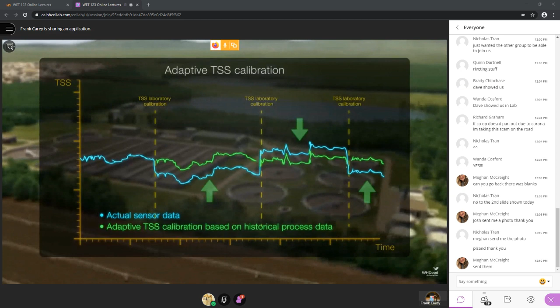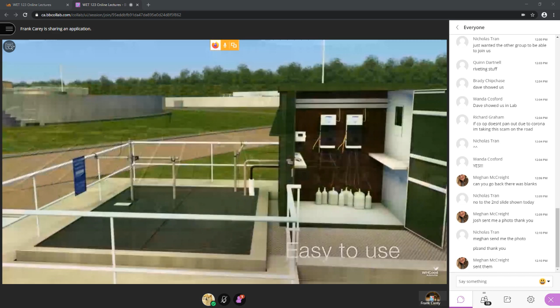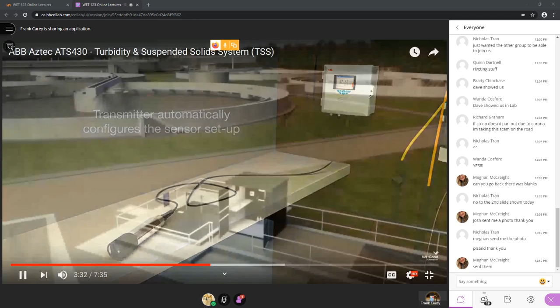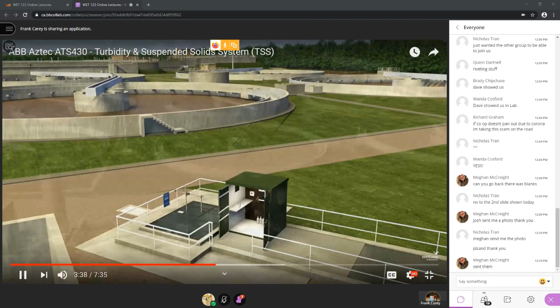This feature provides a smooth TSS conversion and avoids sudden changes in TSS calibration coefficients, often caused by non-representative sampling or erroneous lab results. Setting up the transmitter and sensor is easy. Each sensor is precisely calibrated at the factory, so it is ready to use straight out of the box. Simply connect the sensor using ABB's EasyLink connection, and the transmitter will automatically configure the sensor setup. The Aztec AWT440 universal transmitter can be connected to up to 4 Aztec 400 digital sensors.